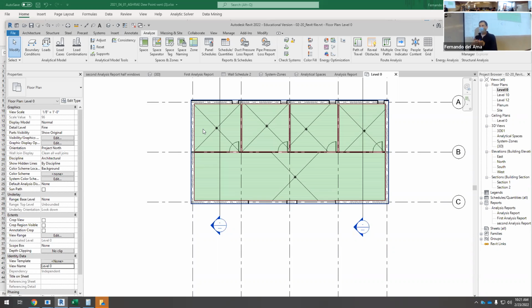Okay, so the boiler has to be running for 1 hour, 2 hours to increase the temperature, and then another 1, 2, 3 hours without working. If the boiler is on and off every 20 minutes, the boiler will last less than working like this. So first, analyze this. Imagine that we have this value in REVIT, and we have this value in Excel. Okay, select this one because it's higher.